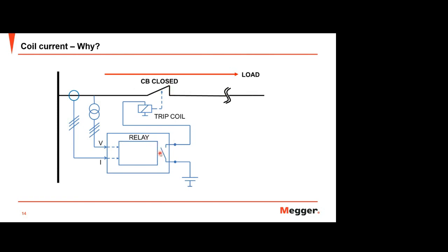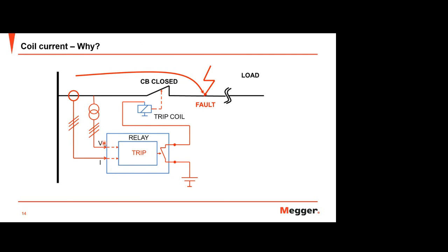When the system has a fault, the CT and VT give information about the amount of the fault condition, either current or voltage. And then the relay will detect it. If the input from these two instruments, CT and VT, is higher than the setting on the relay, then it will trip the relay contact. And as you know from the previous circuit, this relay contact is already on standby with the voltage, ready. When this contact closes, voltage will flow to the coil here.